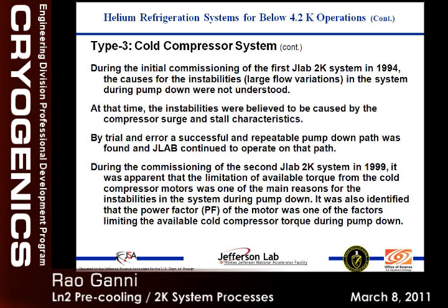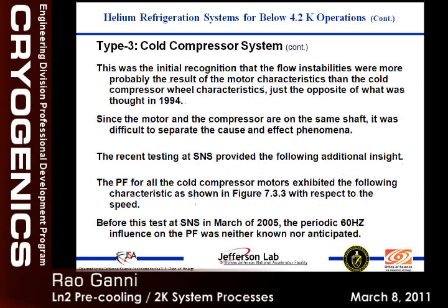And we got 10% more, another 500 watts of 2K for the same 4K plant. And that's where JLab said, go back and rebuild the original, do the new design. Although, when we were making the changes, we were not sure, but we made the changes from the theoretical basis and from all the practical experiences.